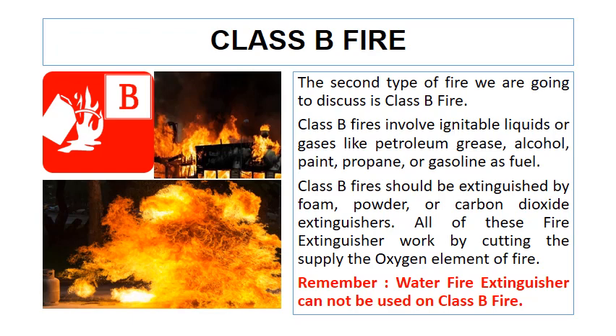The second type of fire is Class B fire. Class B fire involves ignitable liquids or gases like petroleum, greases, alcohol, paint, propane, or gasoline as fuel. A Class B fire should be extinguished by a foam fire extinguisher, powder fire extinguisher, or carbon dioxide fire extinguisher. All of these work by cutting the supply of oxygen. Remember, a water fire extinguisher cannot be used on a Class B fire.